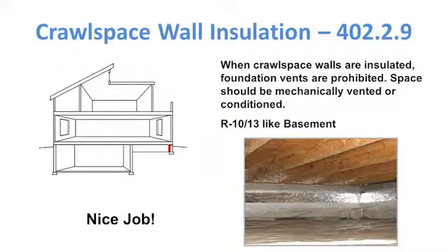When the crawl space walls are insulated, the foundation vents are prohibited. The space should be mechanically ventilated, as I mentioned, or conditioned. And basically the requirements are like a basement. So that means you have to have R10 continuous insulation or R13 cavity insulation.